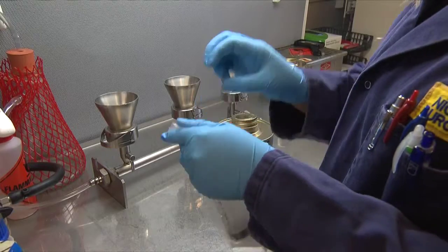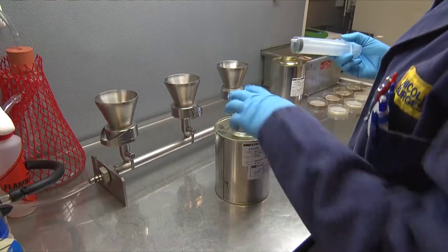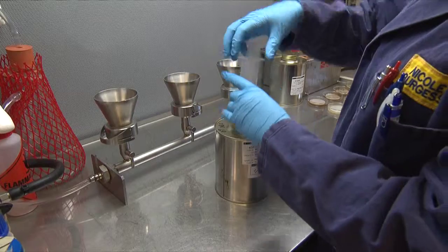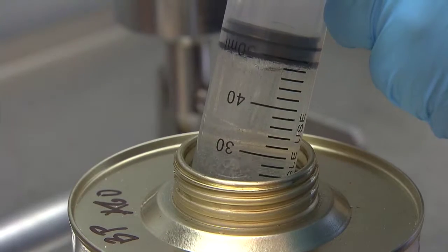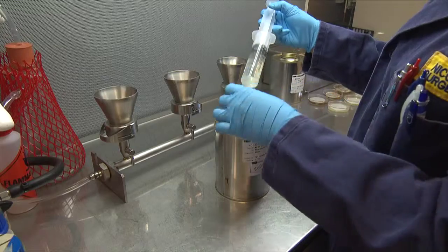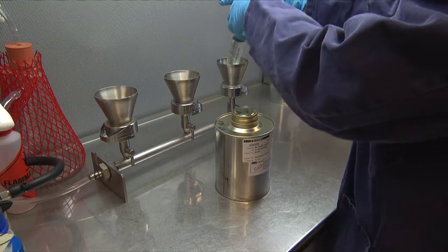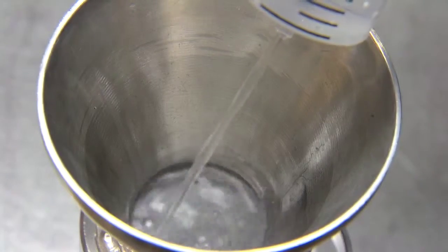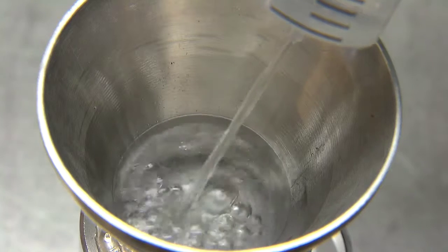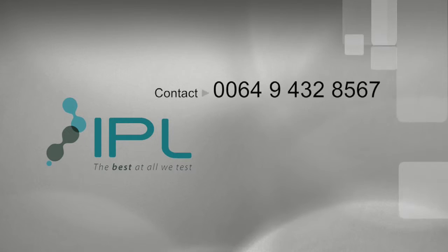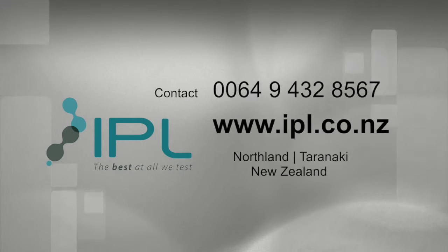How can IPL identify microbiological contamination in fuel? The IP385 test method is useful as it removes oily residues that may inhibit microbiological growth from the filters and agar post-filtering. The method in use by us offers differentiated yeast, fungi and bacteria count, as some fungi inhibit bacterial growth and vice versa. Further information on this type of analysis can be found on our website, ipl.co.nz.